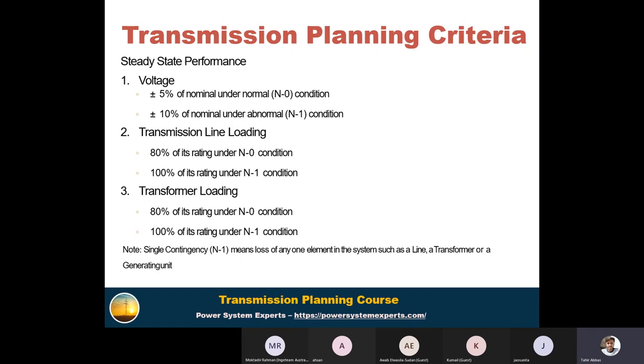In most grid codes, this is N minus one. And sometimes in a modern grid code, there is N minus one minus one, I mean, due to one component, another component is also out of the system. So they are also following that now. And the next is N minus two under bipole contingency for HVDC, and if a tower collapses, then both conductors are out from the system. These are the types of criteria that we need to validate during the transmission planning exercise.